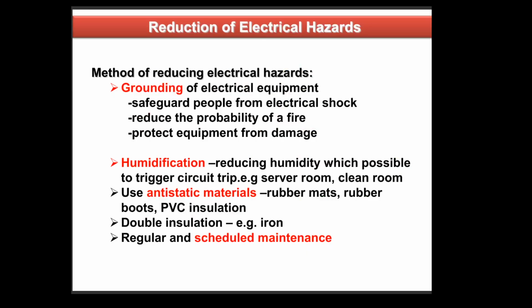Reduction of electrical hazards. Methods of reducing electrical hazards are there. Number one, grounding. Grounding of electrical equipment safeguards people from electrical shock, reduces the probability of a fire, and protects equipment from damage. Humidification: reducing humidity, which is possible to trigger a circuit trip, example server room, clean room. Use anti-static materials, rubber mats, rubber boots, PVC insulation, double insulation, example iron. Regular and scheduled maintenance should be conducted.